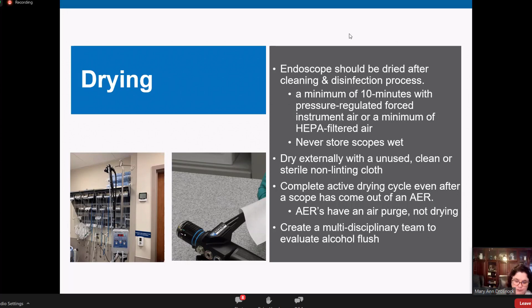I've inspected scopes that were hanging in a storage cabinet for a week, and they had an alcohol flush done on them, and they're still wet inside. It doesn't dry them at all. And alcohol is a fixative chemical, and we now have evidence supporting that. So why would we still recommend it? Well, it's still in the IFUs, and it's still part of the cycle for some AERs. Those all haven't caught up yet. So we do recommend that a multidisciplinary team look at this as a topic and decide whether that's something you still need to do as part of the drying cycle for endoscopes.